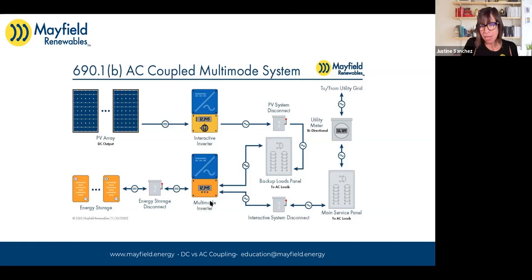And so then if the multi-mode inverter shuts down due to a low voltage situation, now all of a sudden you have the situation where it's down. It's not producing any power, which means it's not feeding this backed up loads panel, and it's not giving a signal to the interactive inverter, which means it shuts down. Okay, and so there's no way for this PV array to step in and charge the batteries, because it has to run through this whole circuitry and be woken up by the interactive inverter, which is now shut down due to low battery voltage.